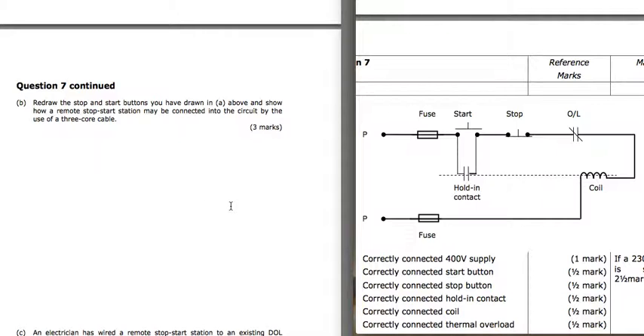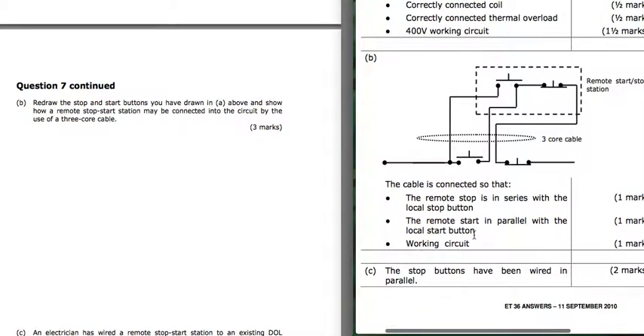Redraw the start and stop buttons they've drawn, so we can use a remote start stop. So there's our remote start stop, there's our normal start and stop, and if you look, the remote start is in parallel with the normal start, and the remote stop is in series with this stop here. So we break between the start and the stop of the original contacts, and we take those leads out to the stop. So start in parallel, stop in series.